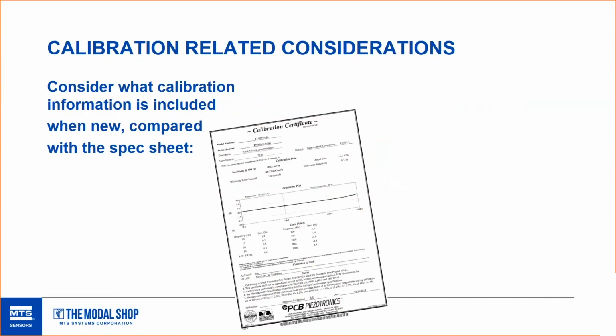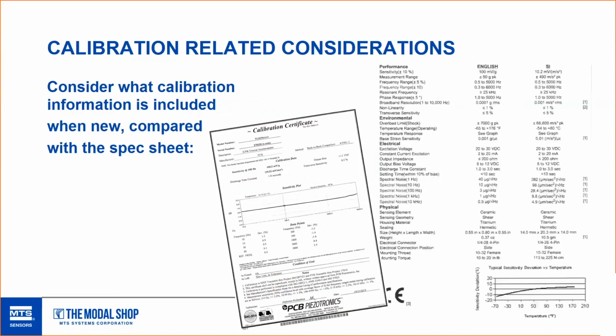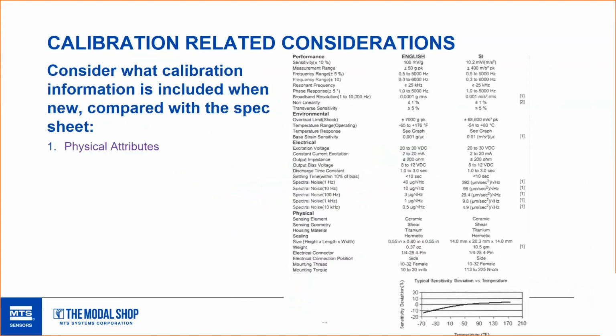So I'd like you to consider what calibrations included when you compare new to a spec sheet. We're just going to go over some of the basics here for this, again, accelerometer. Like the physical attributes section may not be really that important. That's likely not going to be tested when it comes in for any calibration. So maybe it's not really vital to you for the recal. The physical attributes are why you pick the sensor to begin with, but maybe not something that needs to have time spent on checking. The typical specs. These may be specs that didn't even come included with your sensor when it was built and bought. These often are done at a design phase at a really high level, take a lot of time to develop statistical data of, and are deemed that they're specs that won't change over time, even in the manufacturing process.